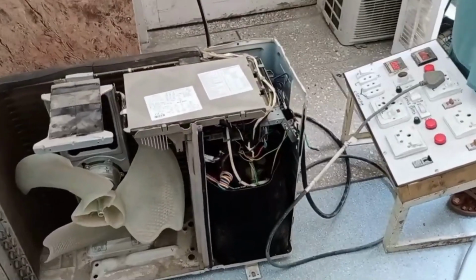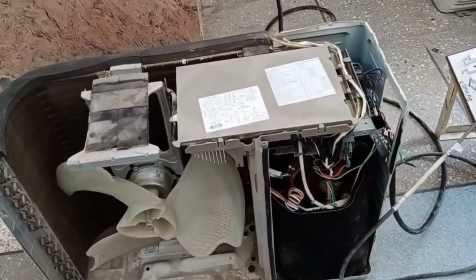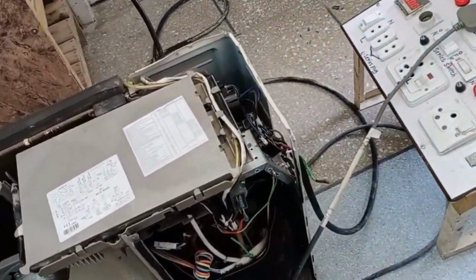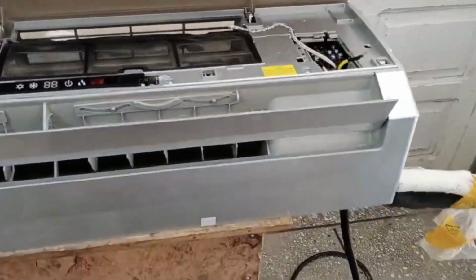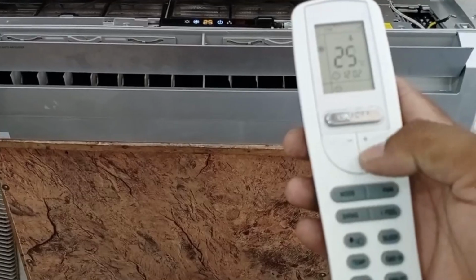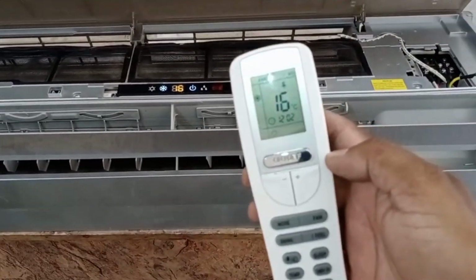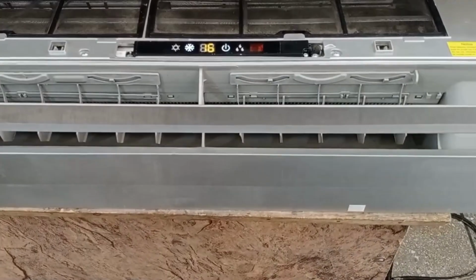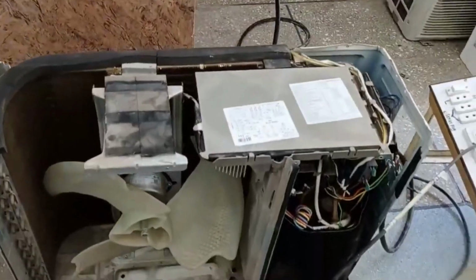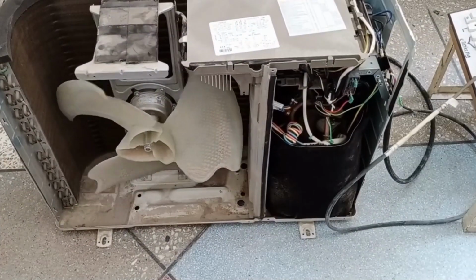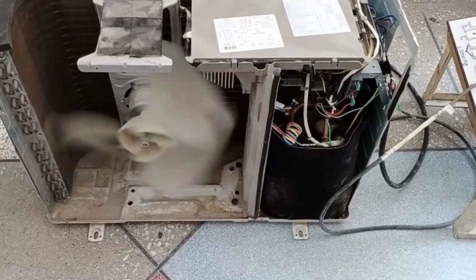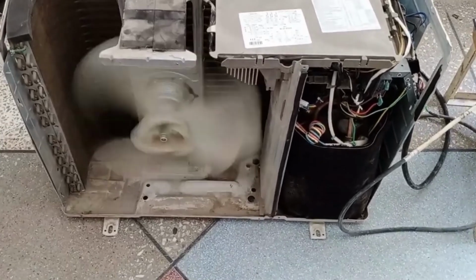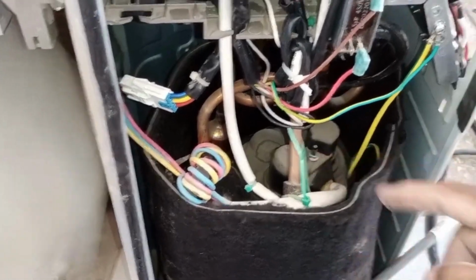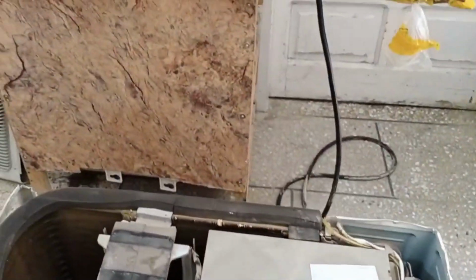Today, we have the complete unit, so I installed the outdoor PCB and connected all the necessary wires. I also connected the indoor unit and the power is on. After setting the temperature to 16 degrees, we powered the unit on. You can see that the display turned on, and now we're testing how long it takes for the unit to start. As you can see, the outdoor fan started first, and after a short delay, the compressor also started.